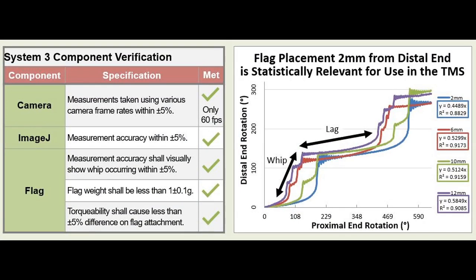Because the distance of the optical flag may affect the torqueability test, to determine the optimal flag distance from the distal end of the guidewire, multiple trials were taken when the flag was placed at 2, 6, 10, and 12 mm away from the distal end. Using the ANCOVA analysis, the 2 mm distance had a p-value greater than 0.05. Therefore, the 2 mm was not significantly different from the ideal 1-to-1 ratio for regression lines. Future tests should implement the 2 mm distance for flag placement.